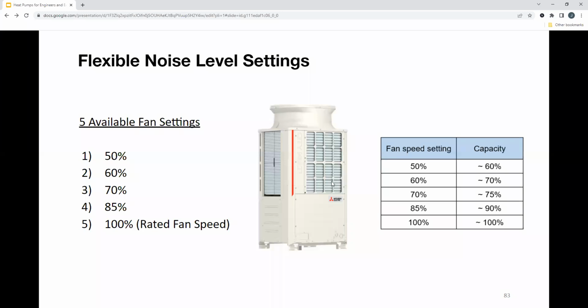You can find the sound ratings and power ratings on any submittal for a manufacturer. And if they don't adhere to what that decibel is throughout the night, what you're able to do is set a dip switch, and then reduce the fan speed setting, right? To get to that decibel that you need. The only thing with that is if you are reducing the fan, you're not touching the compressor, but you're reducing the fan, that does affect the heat transfer on these outdoor coils.